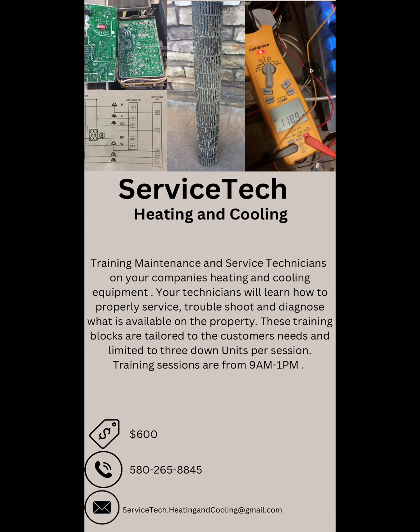Some of those reasons a motor fails: a bad capacitor, so we need to look at those. We're back at capacitors again. Go check the capacitor that feeds that motor and make sure that it's within 6% of tolerance of what it's rated for. If it's not, change it out and see if that fixes your problems.